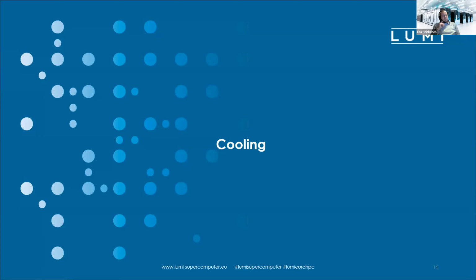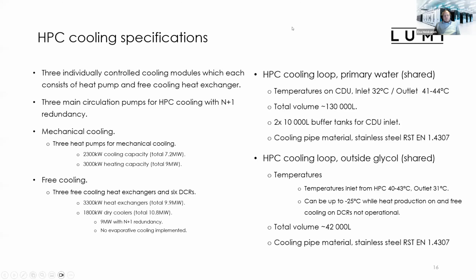Then details about cooling in the Lumi facilities and how the cooling is controlled. So this HPC cooling, we have 3 individually controlled cooling modules, which each consist of a heat pump and a free cooling heat exchanger. Each of these are connected to different substations, and those are operated individually. So in case we lose, for example, one substation, 2 of these continue running and operating without any issues. We have 3 main pumps for the HPC cooling with N+1 redundancy, so we are actively operating 2 pumps at a time for the HPC cooling.